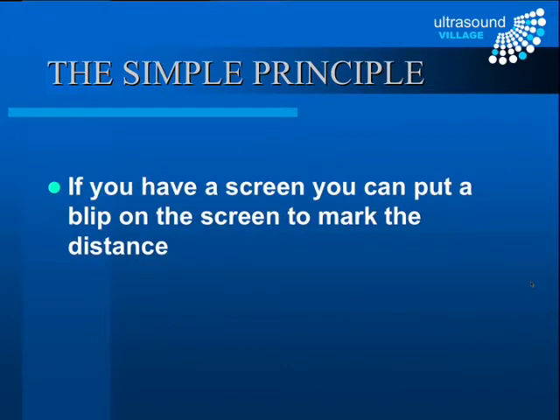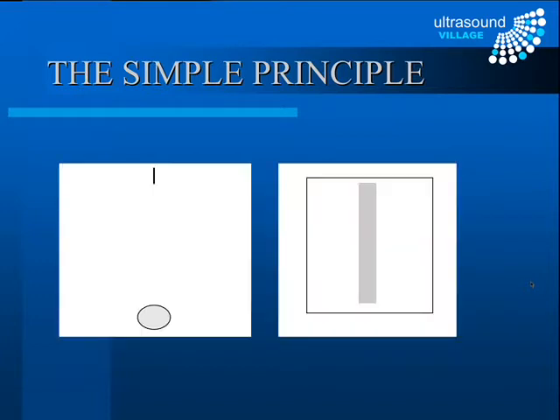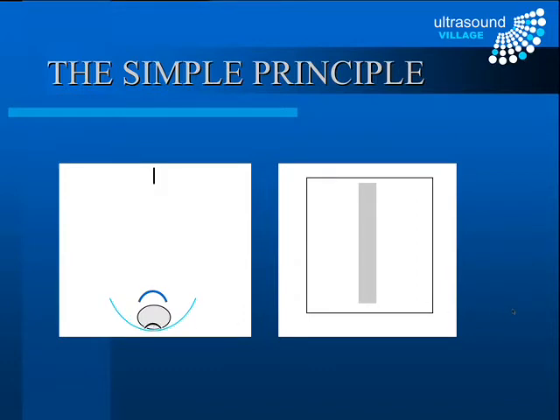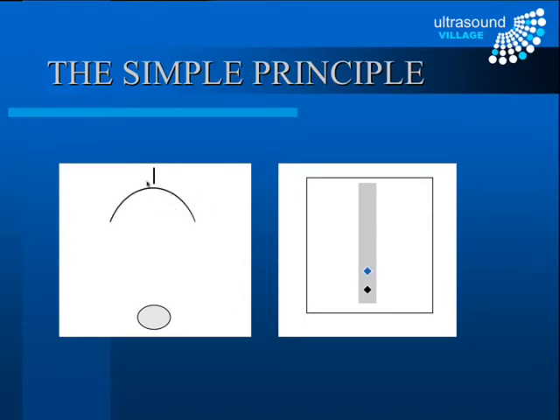If we have a screen, we can put a blip on it to mark out that distance. We send out a sound wave; it travels through the medium, hits the object, and a reflection is generated, but most of the energy continues on until it hits the far edge of the object. Another reflection is generated, and these two reflections travel back to the transducer. When the first reflection arrives, the machine puts a blip on the screen; a short time later the second reflection arrives and produces another blip a little further down.